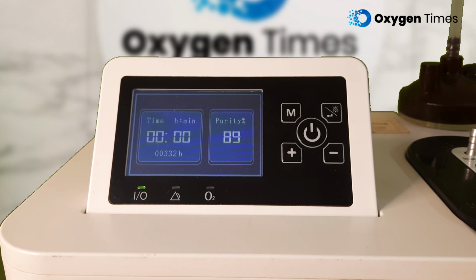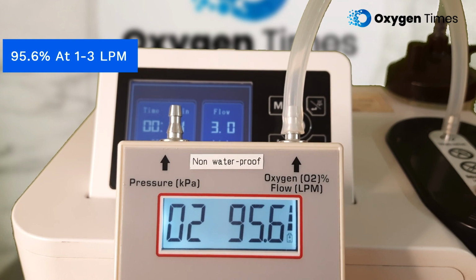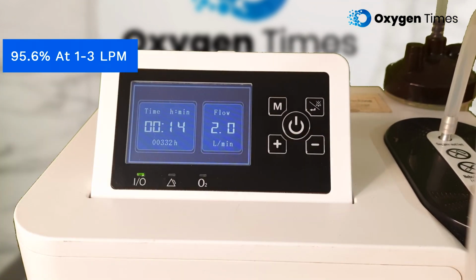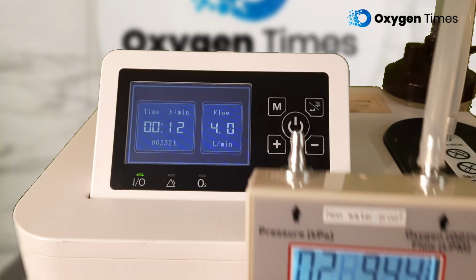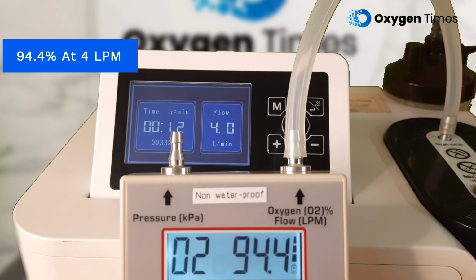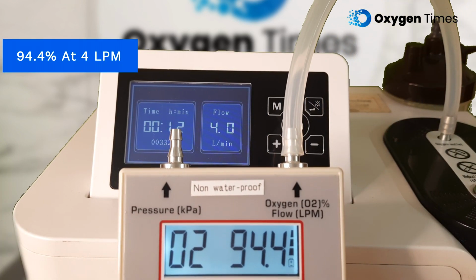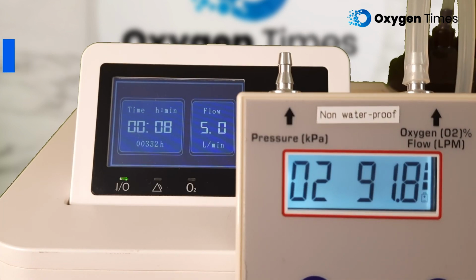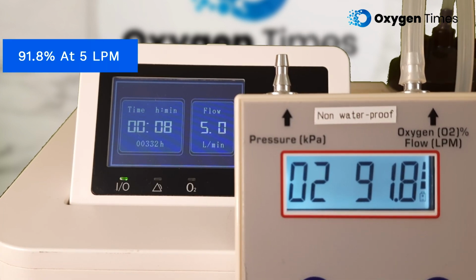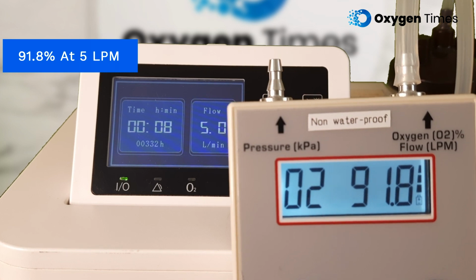In the purity test at different flow rates, we found that the Oxymed Mini delivers 95.6% pure oxygen at 1 to 3 LPM, 94.4% oxygen at a flow rate of 4, and 91.8% oxygen at the highest flow rate of 5 liters per minute.